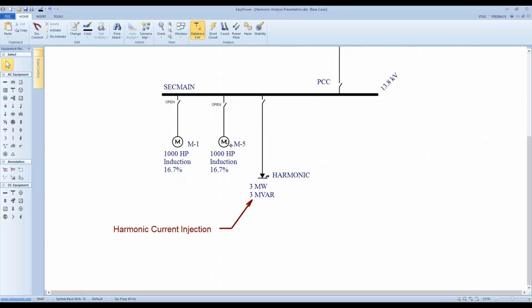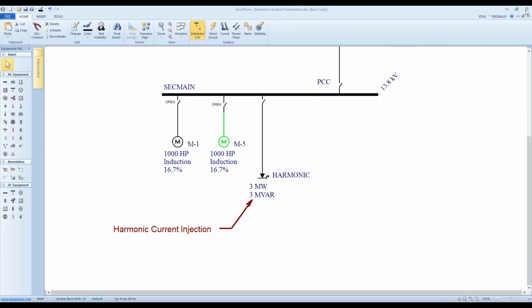There are other ways of doing this. You can also do this on the motors tab. You have a harmonics tab too. So all of the individual loads within EasyPower have the ability to put in a harmonic current injection for that device. I tend to sum up the total harmonics and put it into a harmonic load as shown here. Right? That's my preferred philosophy.